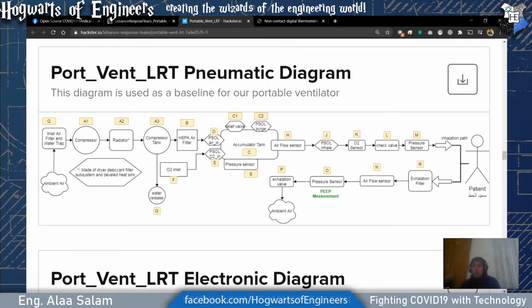And the air going to the patient is always coming from the accumulator tank at all times. The only time the patient breathes the air in the room or from another source is when a fault alarm is issued and something called a safety valve opens. It's right over here, the PSOL purge. What happens here is that if something shuts off on this end, we don't want them to breathe nothing. We don't want it to be empty. So we open that purge valve so that it allows the air inside the room to come into the accumulator tank and be given to the patient directly.